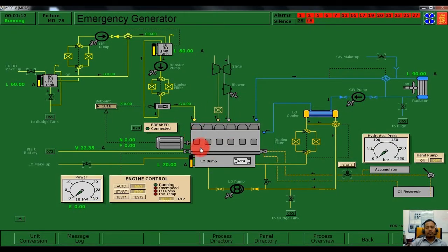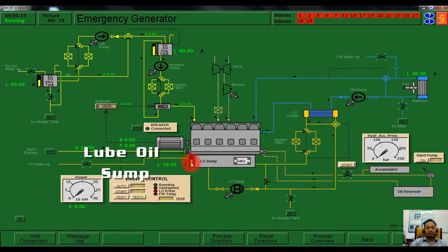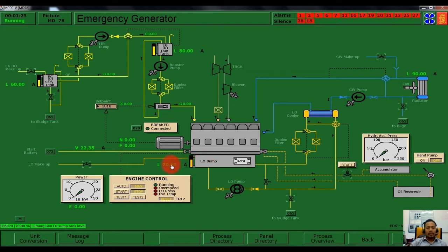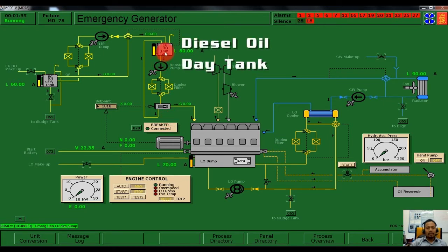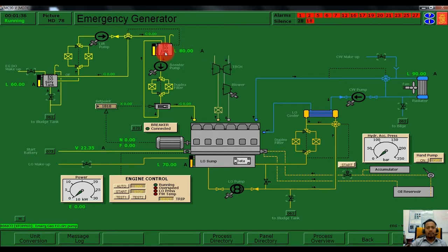Before we start the emergency generator, we need to do several checks. The first thing is to check the lube oil sump. Currently our lube oil sump is 70 percent full, as you can see here. After that, we need to check the diesel oil day tank for the emergency generator. Currently the level is 80 percent full.